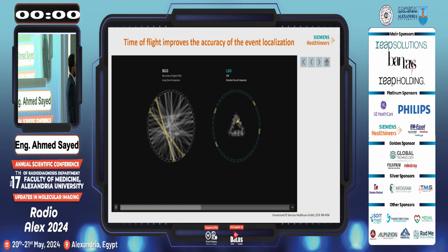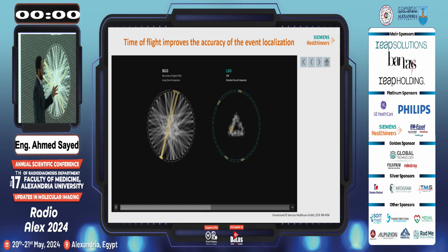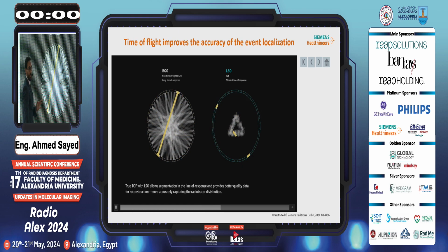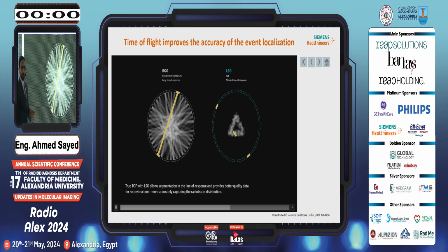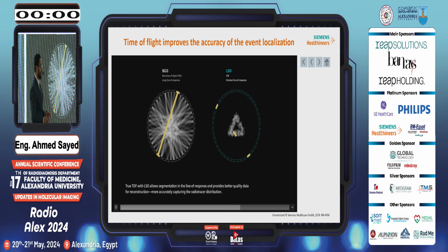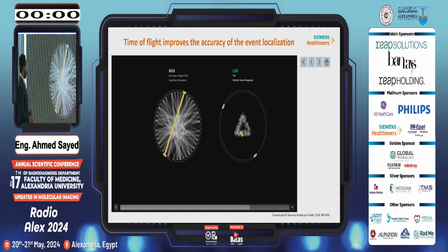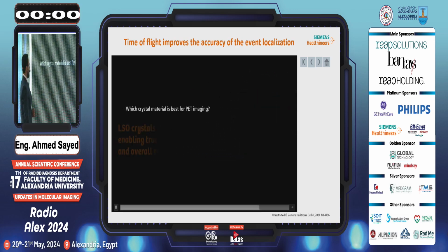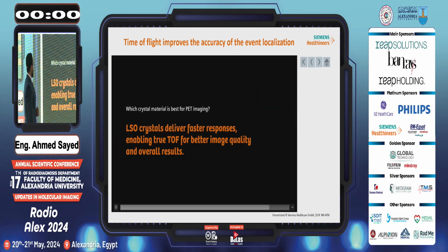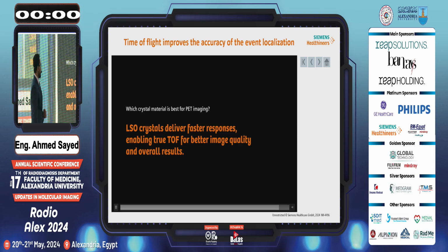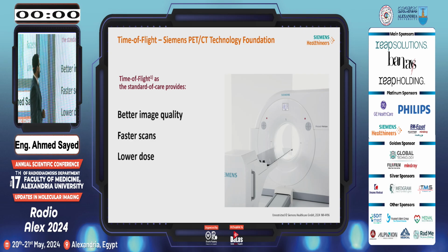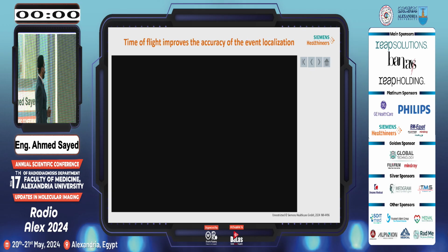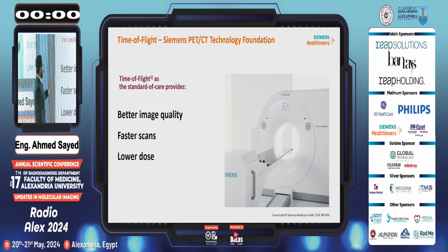By the way, time of flight is only for LSO crystals, not for BGO. So if you have a BGO-based system, you cannot get the time of flight option or reconstruction. Time of flight gives us better image quality, faster scans, and lower dose.